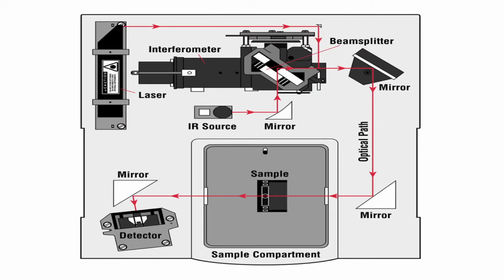Most interferometers employ a beam splitter which takes the incoming infrared beam and divides it into two optical beams. One beam reflects off of a flat mirror which is fixed in place. The other beam reflects off of a flat mirror which is on a mechanism which allows this mirror to move a very short distance, typically a few millimeters, away from the beam splitter.